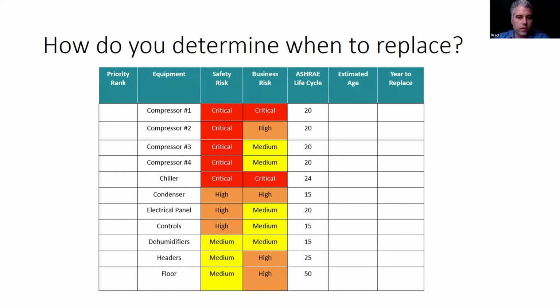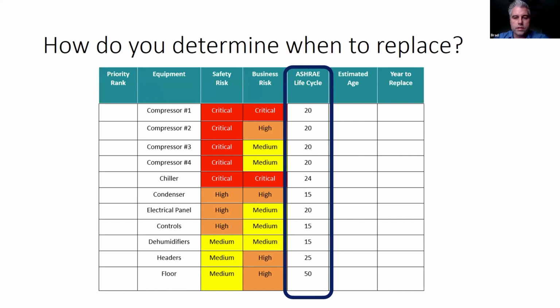Here's a list of all the equipment typically in a room. Make sure maintenance is being done based on manufacturer specifications. Then compare the ages of all the equipment with the industry guideline, ASHRAE, which has set out the life expectancy for aging HVAC and mechanical equipment. Compare it to find out how much life is left in your system, and that'll help with your planning.